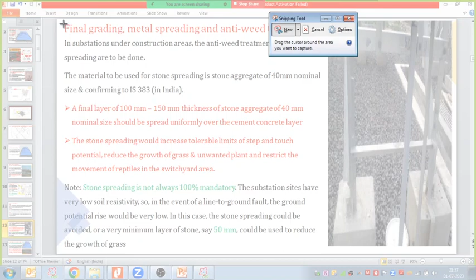And as I told you, whether stone spreading is 100% mandatory or always mandatory, the reply is that stone spreading is not always 100% mandatory. At substation sites with very low soil resistivity, around 4 ohm, 5 ohm, 6 ohm, what is the stone doing here? How is it increasing the tolerable step and touch potential limit?